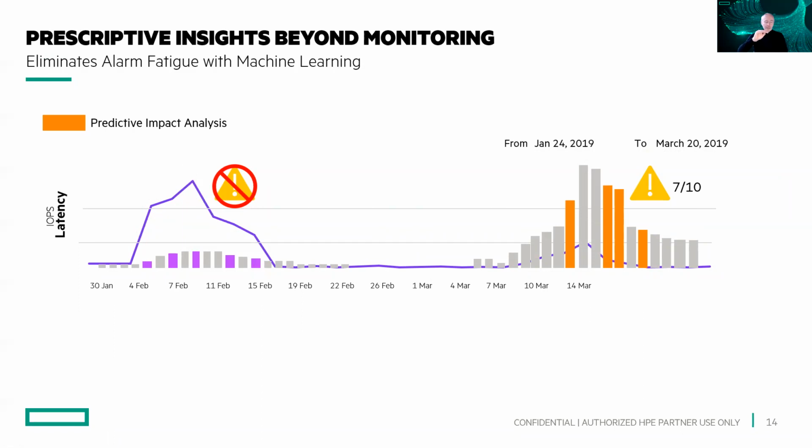But hold on, let's say you have set the monitoring to alert if that peak goes above, I'm just saying something, 100. Let it be 100 milliseconds or microseconds, it's not important. You have to set it above 100. That is okay. But watch out: your daily average for months already is between 10 and 20. And now for some kind of reason it goes up to 50 or 60. Even that 60 is not normal, because the last month it was always between 10 and 20.